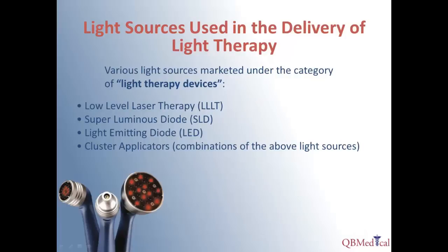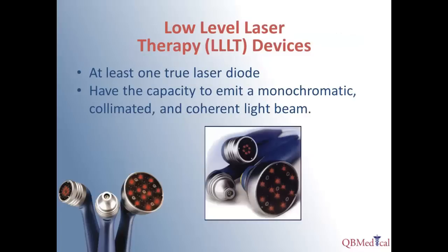While low-level laser therapy is one form of light therapy, there are other forms available as well. These commonly include superluminous diodes and light-emitting diodes, which may be in the same or similar wavelengths to a laser; however, they will not have as much penetration due to being non-collimated and/or non-coherent. There are also cluster applicators available in some devices, which use a combination of laser, LED, and SLD. To be considered a cold laser device, there must be at least one true laser diode on the applicator that is monochromatic, collimated, and coherent.